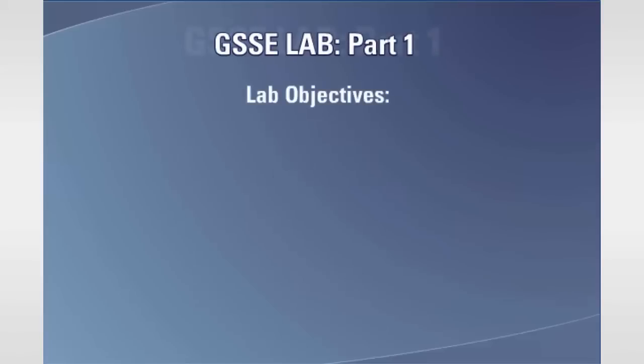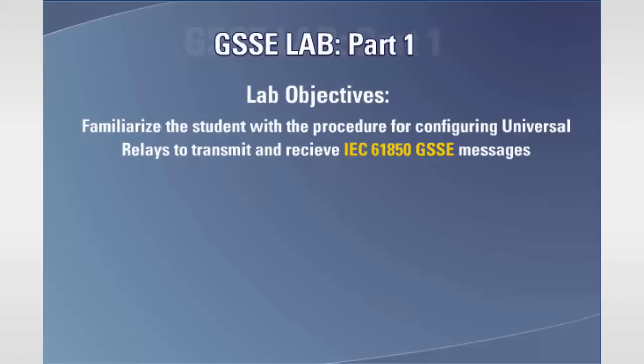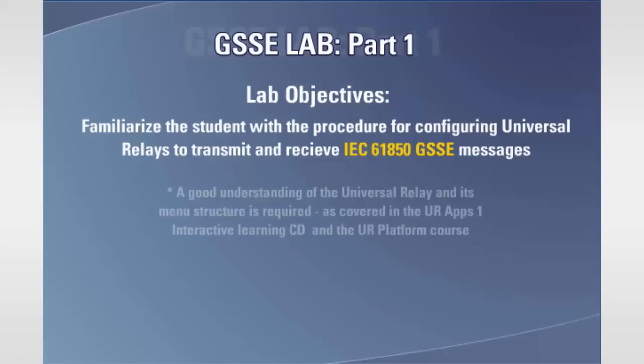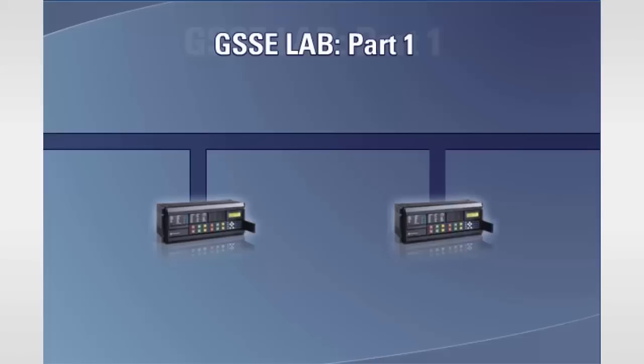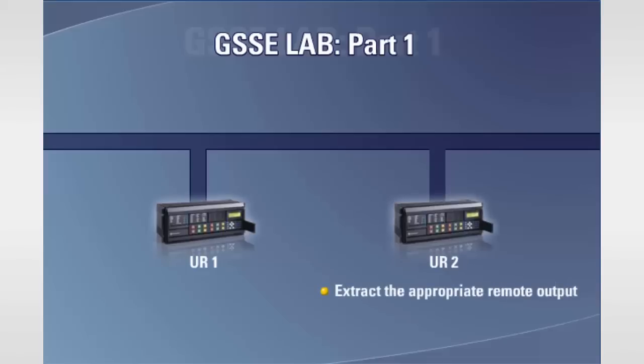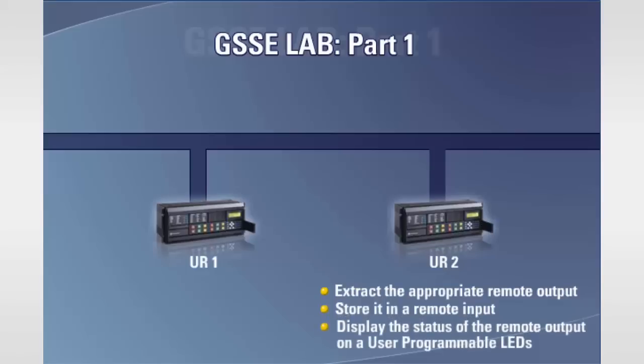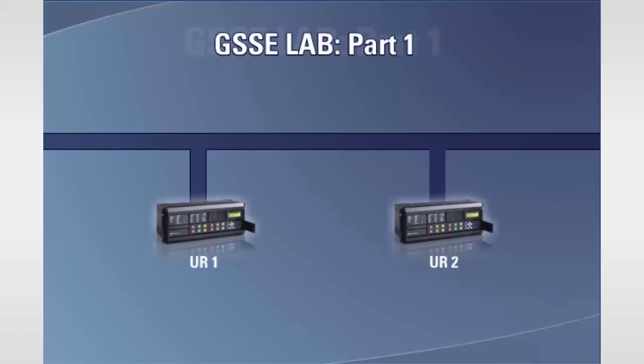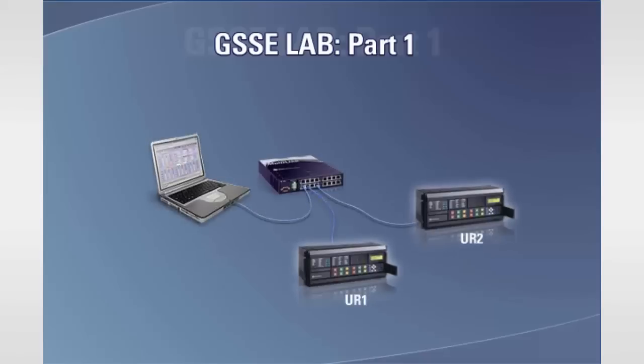The objective of this lab is to familiarize the student with the procedure for configuring universal relays to transmit and receive IEC 61850 GSSE messages. In this lab, the status of Control Push Button 1, located on Universal Relay 1, will be transmitted via a remote output within a GSSE message to Universal Relay 2. UR 2, upon receiving the message, will extract the appropriate remote output, store it in a remote input, and display the status of the remote output on one of UR 2's user programmable LEDs. The student requires two universal relays equipped with Ethernet ports, a multi-link switch, a computer preloaded with the UR EnerVista setup software, and the appropriate Ethernet cables. First, set up and test the Ethernet LAN using the ping command. Once this is done, configure UR 1 to transmit GSSE messages.